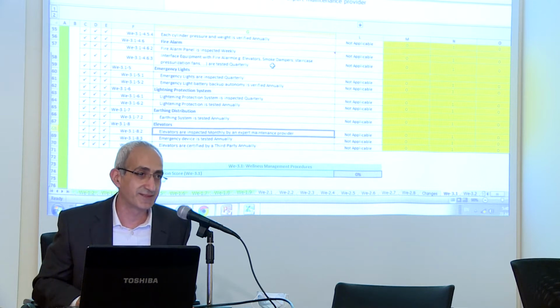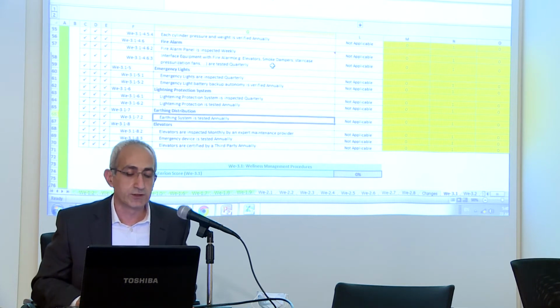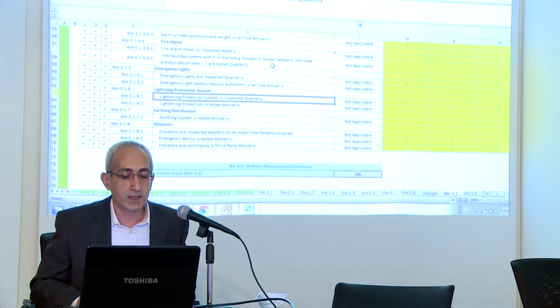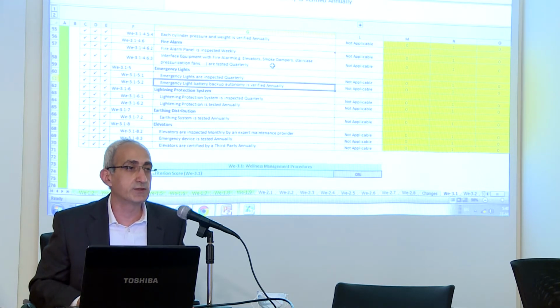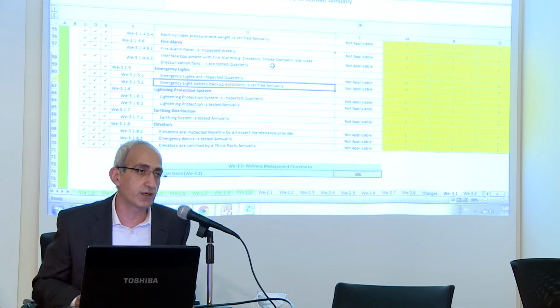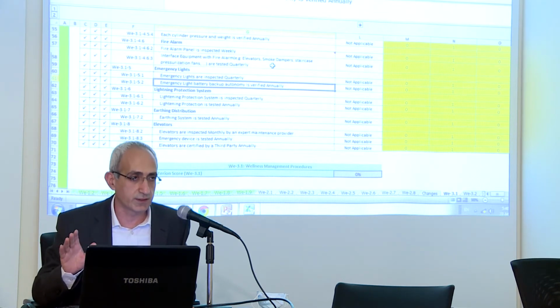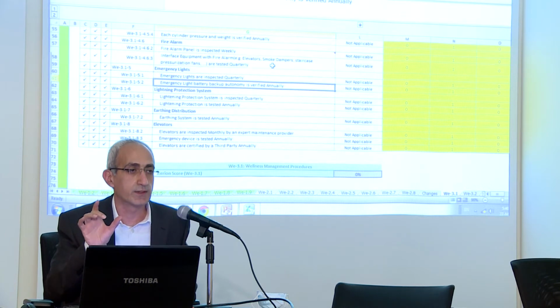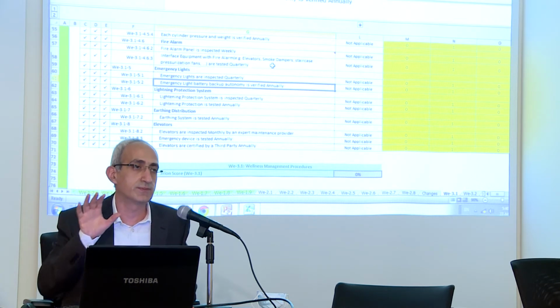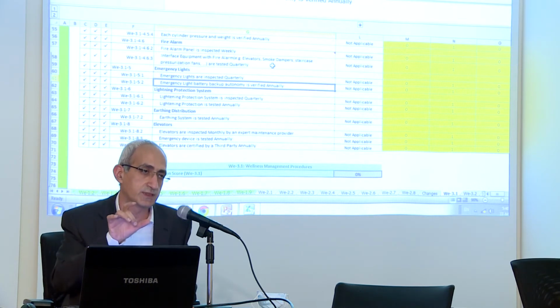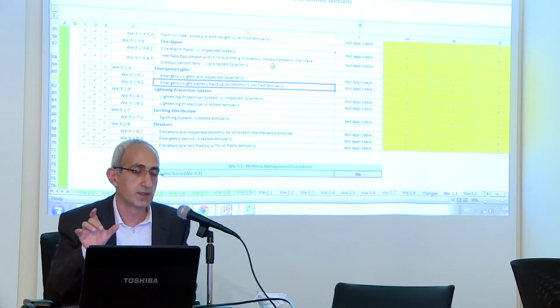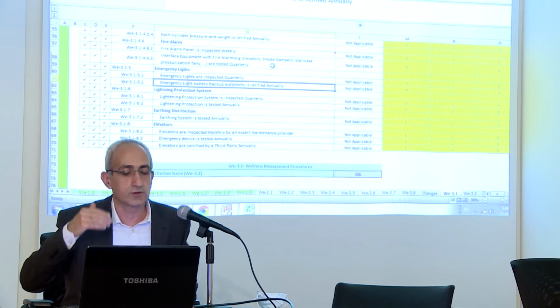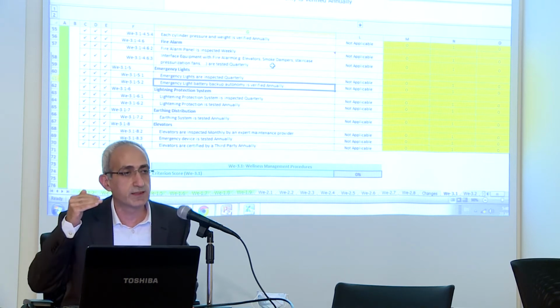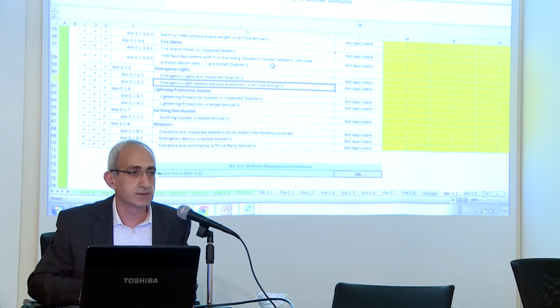What do you mean by autonomy? Autonomy. So the emergency lights need to operate, for example, for 1.5 hours as per NFPA, or 2 hours, or 3 hours, depending on your design. So this is the autonomy. The battery should be able to serve the emergency lights for that period of time. Battery life will degrade with lifetime, so every year we have to ensure that this autonomy is maintained.